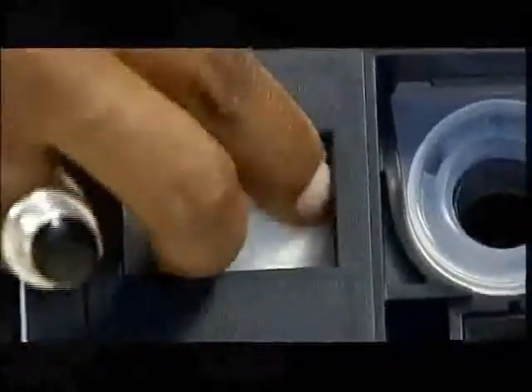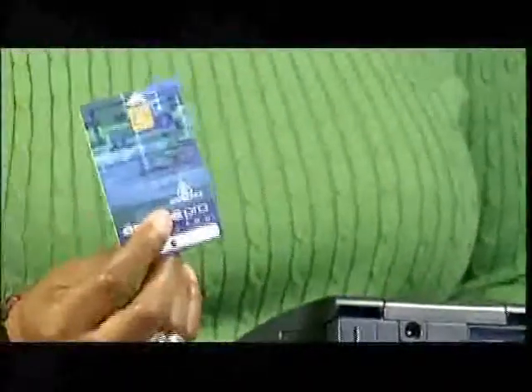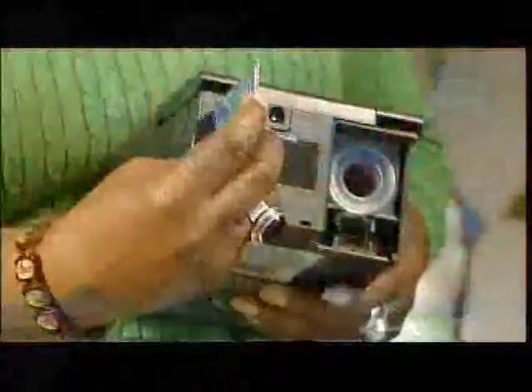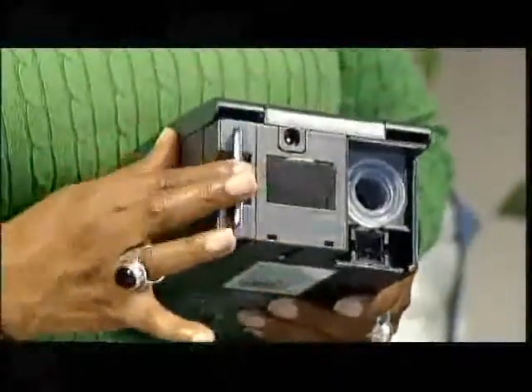The white ultrafine filter goes in first with the soft, cushy side facing out, and then simply put in the gray reusable filter. Next to the filters is your smart card, your compliance. Simply pull it out of its module and take this with you for any visits that you have at the clinic. Once your clinic visit is over, please remember to insert the card back into its module so it can continue to record.